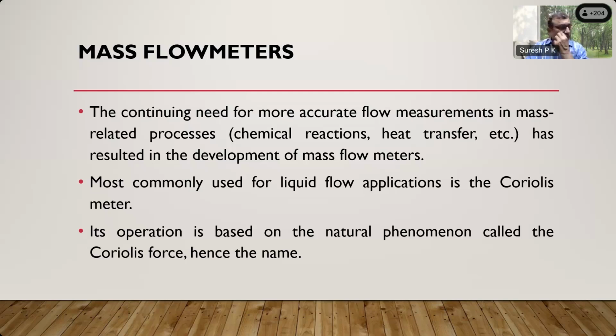Basically, you may have experienced this when your children are playing in a park on a rotating platform, and you walk across the platform radially. You will experience two kinds of forces. One is the centrifugal force created by the rotation. Another is that you are changing your position continuously across the radius. A particle moving across the radius continuously on a rotating platform will create another force called the Coriolis force. This is basically measured and is proportional to your movement velocity. That is what is being utilized in this flow meter.